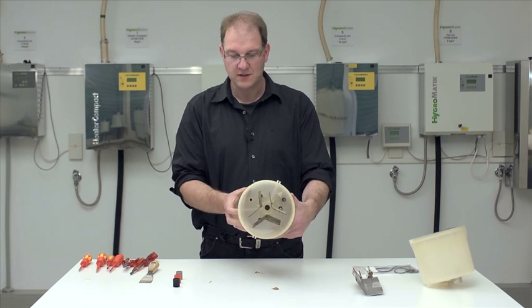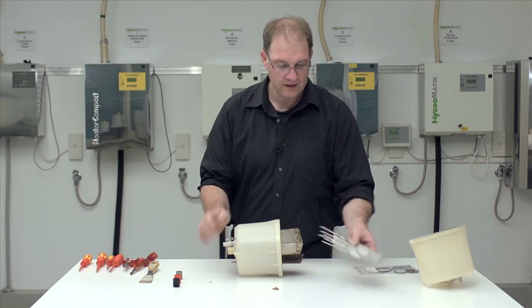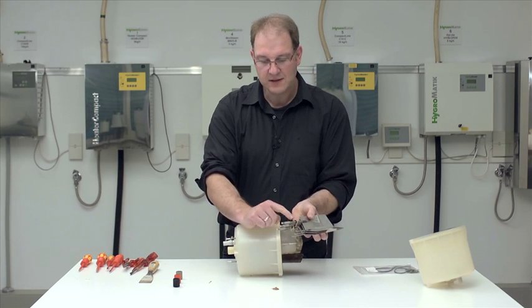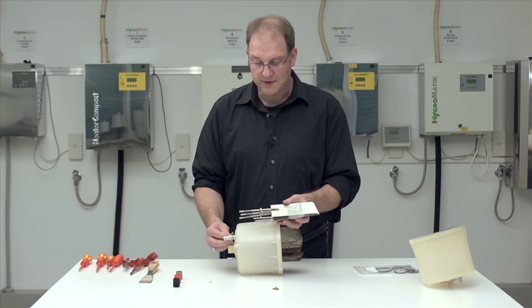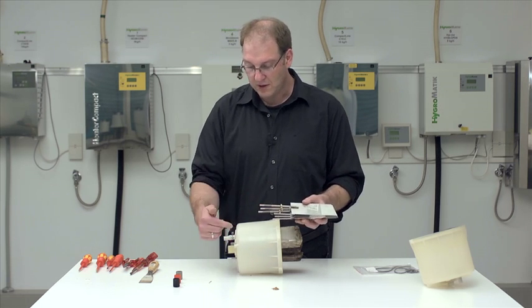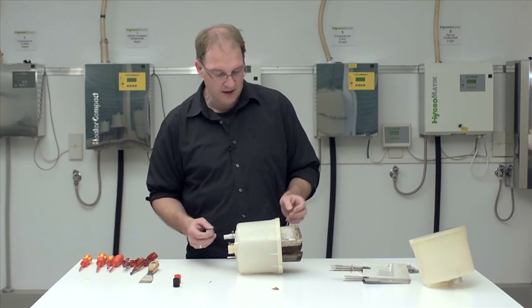Well, I have inserted them all. It then looks like this. The electrodes themselves have a washer up front here. Inside this washer is an o-ring, and the moment I fasten the electrode with a knurled nut, this o-ring secures itself here to the top part of the steam cylinder, and we have achieved a tight seal.